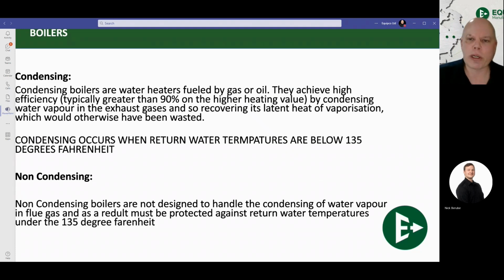So a bit more detail, basically to reiterate what was mentioned here. Condensation occurs when the temperatures are below 135 coming back. With non-condensing, you want to make sure that your return temperatures are above 135. That's how you make sure that the units operate properly and as effectively as possible between condensing and non-condensing. There are going to be some differences in the venting applications as well, but for the most part, that's going to be your main criteria as to why a non-condensing or a condensing boiler is used in an application.